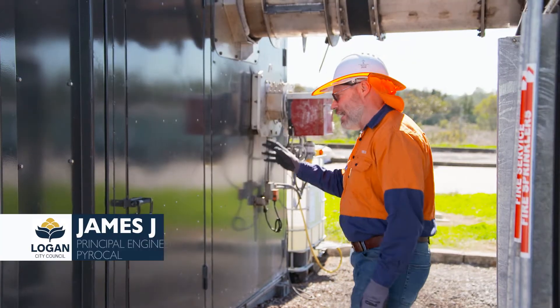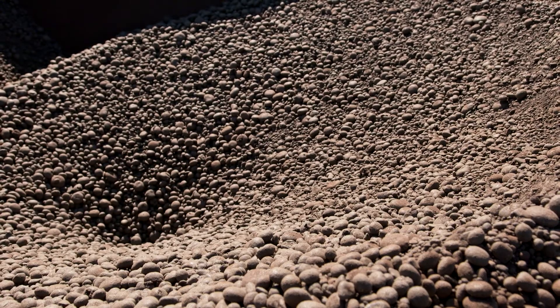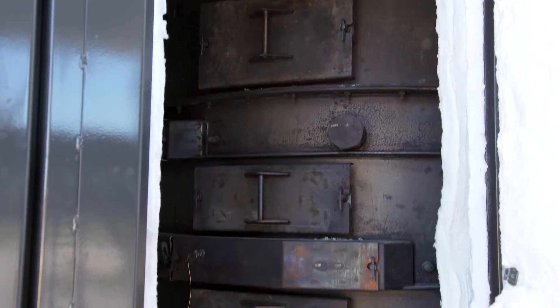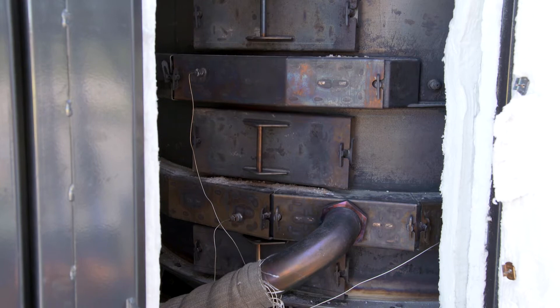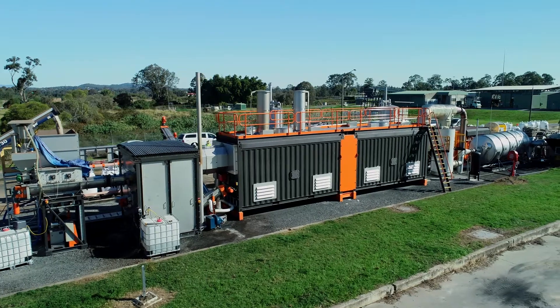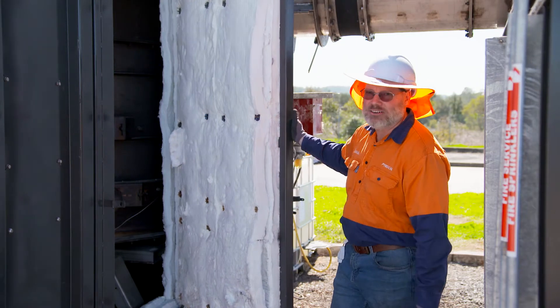Inside here is the hearth — it's a gasifier, basically a furnace. The biosolids are fed in through that screw there. They're dragged around a deck, drop down to the next one, and do that a couple more times until the solids come out the bottom as char. The gases that are released from the process go out to the oxidiser. This unit operates around 600 or 700 degrees.